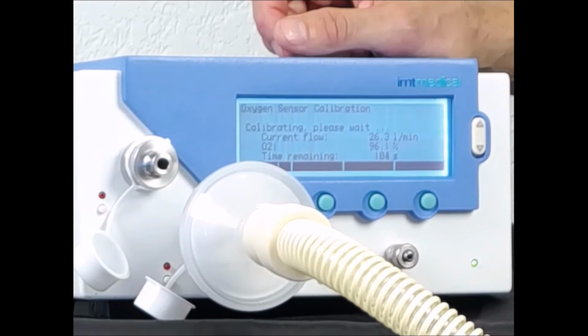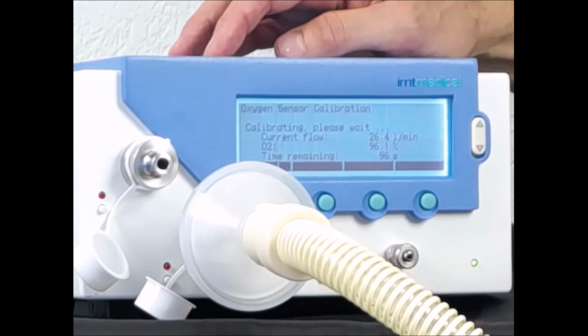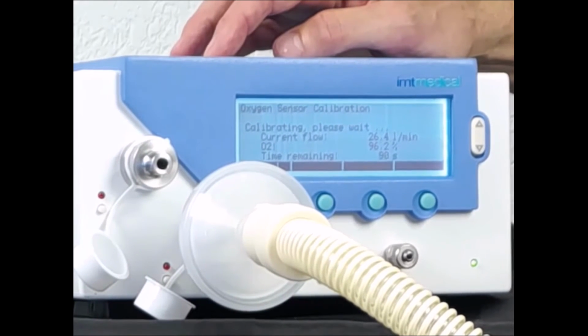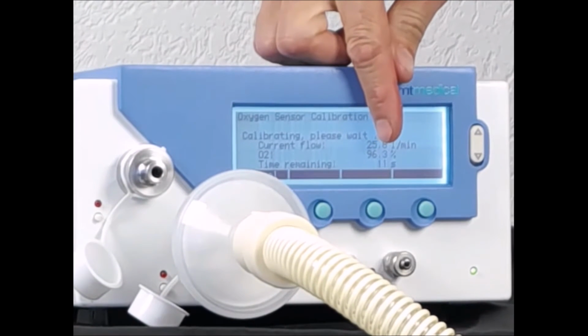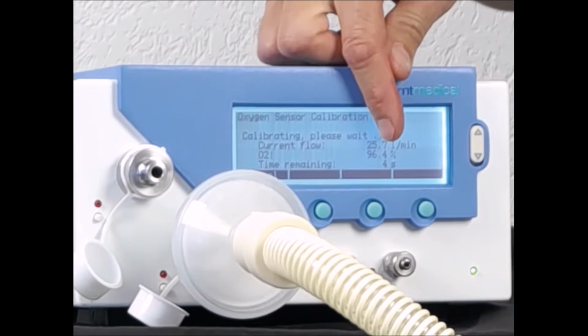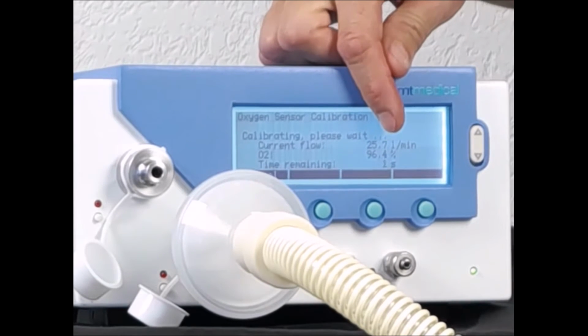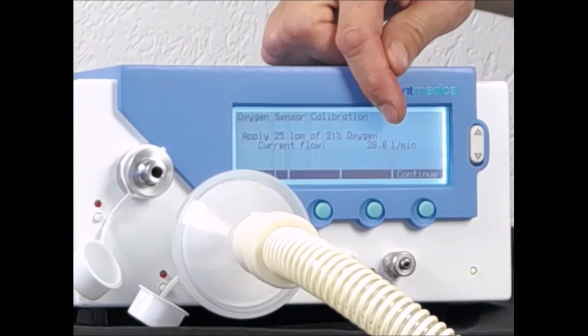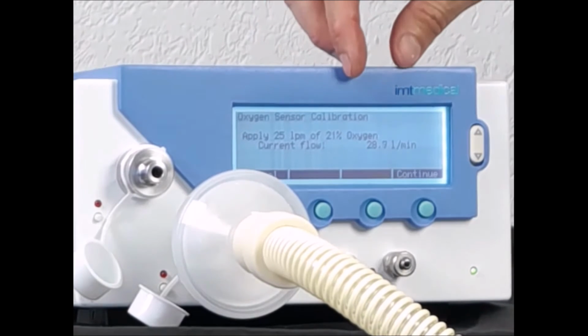The oxygen calibration in the PF300 is always a 2-point calibration. 2-point calibration means 1 point at 100%, which we do right now, and another one at 21% pure air. We will do that right afterwards. So now the oxygen calibration, the 100% point is almost done. We have 10, 9, 8, 7, 6 seconds left. And after this, we will be prompted to do the same at 21% with air.